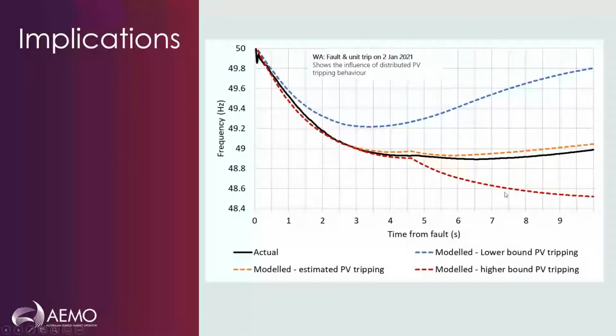The different lines here are different modeling scenarios that we've looked at, and the only difference between these is the amount of PV that we estimate to have tripped off, with the blue being a lower bound estimate and the red being an upper bound estimate, and the orange being our best guess of what actually happened in this event. And so you can see how dramatically different the power system outcomes are in terms of whether frequency bottoms out at a reasonable level and recovers, or is potentially going through to a level where it can't recover, just due to the difference in the PV behavior.